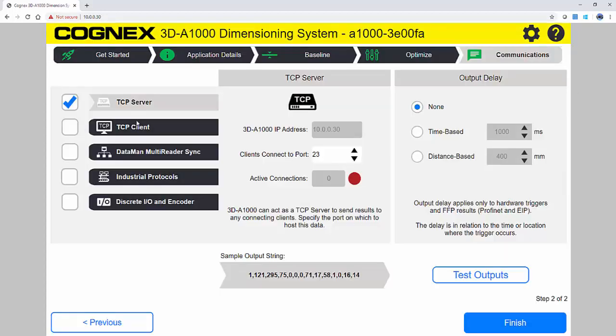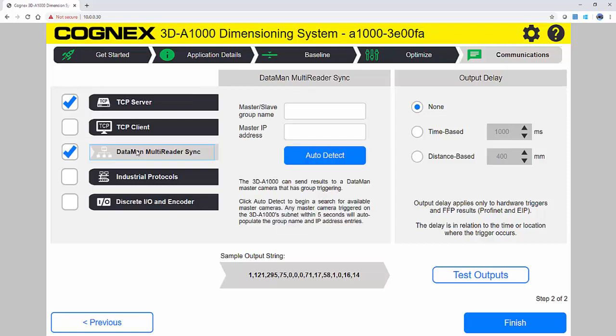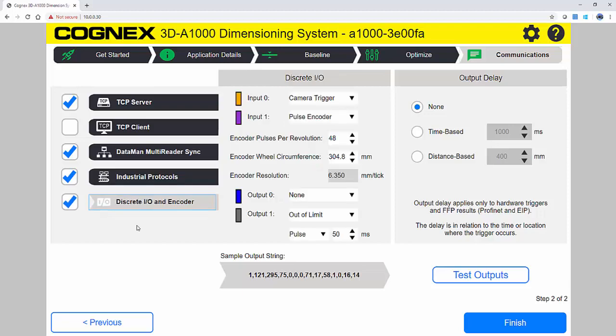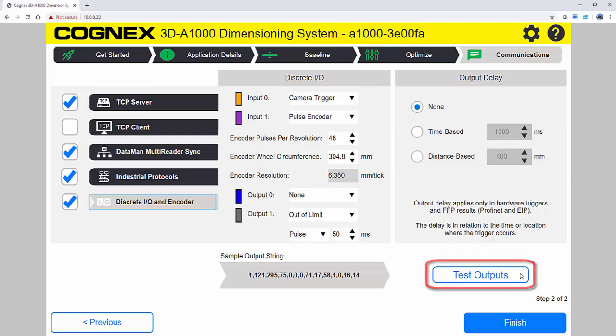Page 2 is where you will find all of the communications information. Here you can set up the TCP server and client. Configure Dataman multi-reader sync, which allows you to send results to a Dataman master camera. This is also where you configure your industrial protocol communications. You can set up your discrete inputs and outputs, and you can also set up the output delays. In the lower right-hand section, there is a Test Outputs button to generate sample data and ensure it is correct.